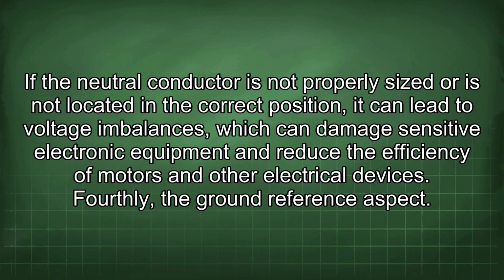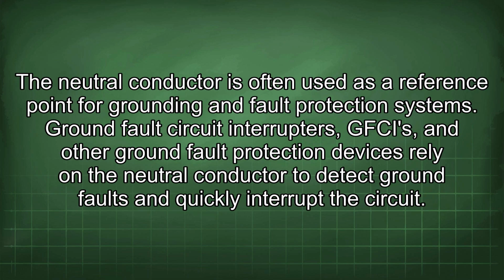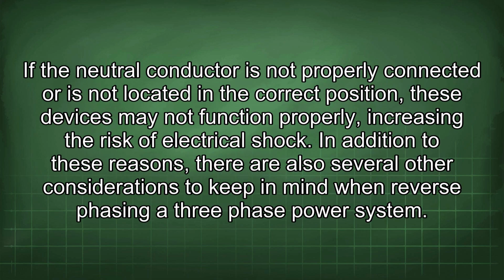Fourthly, the ground reference aspect. The neutral conductor is often used as a reference point for grounding and fault protection systems. Ground fault circuit interrupters, GFCIs, and other ground fault protection devices rely on the neutral conductor to detect ground faults and quickly interrupt the circuit. If the neutral conductor is not properly connected or is not located in the correct position, these devices may not function properly, increasing the risk of electrical shock.